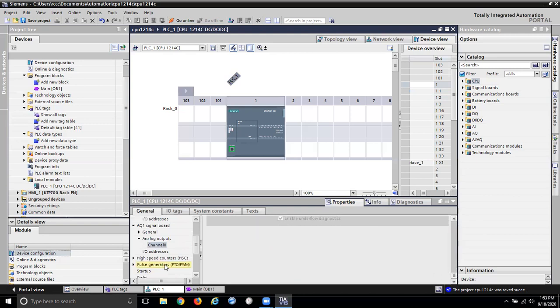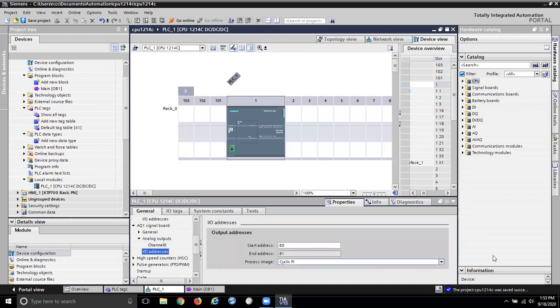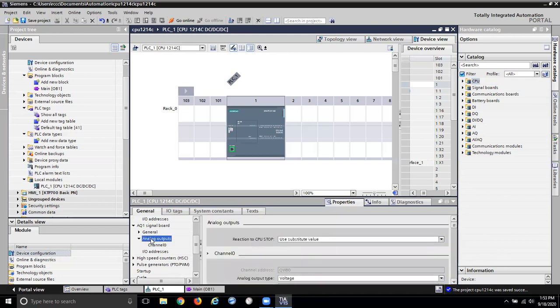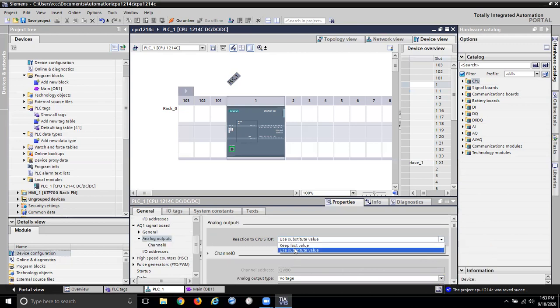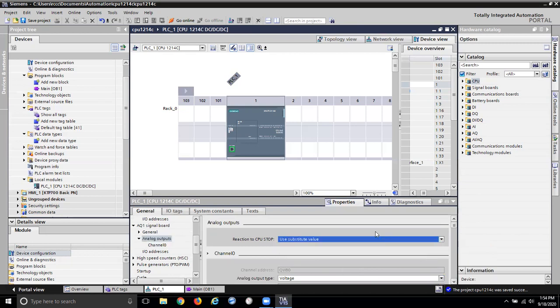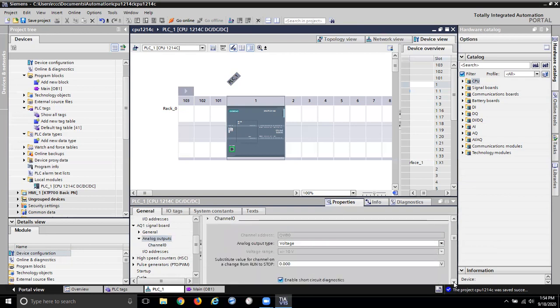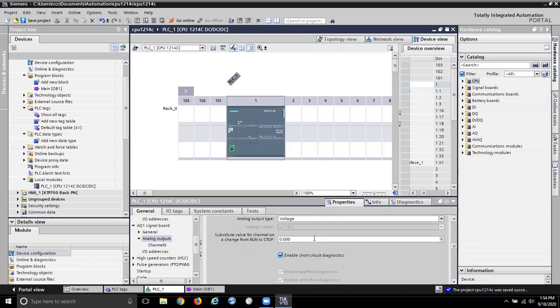That's really all I can configure. For the analog output general settings, if the CPU stops it has a substitute value — you can tell it if the CPU goes to stop what do you want it to do: either keep the last value or put in a number. So depending on your device you might want to keep the same output. It's a voltage output, plus or minus 10 volts.